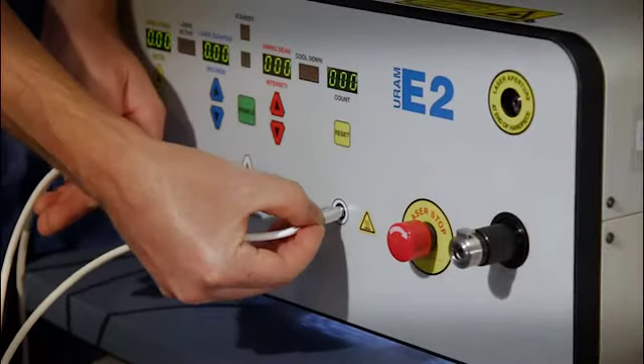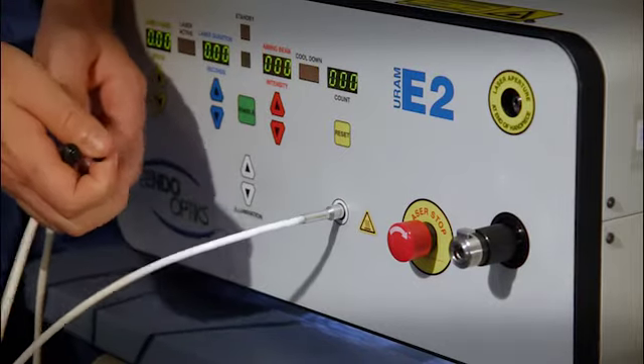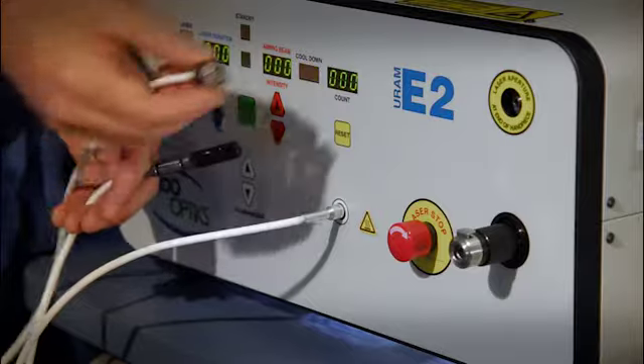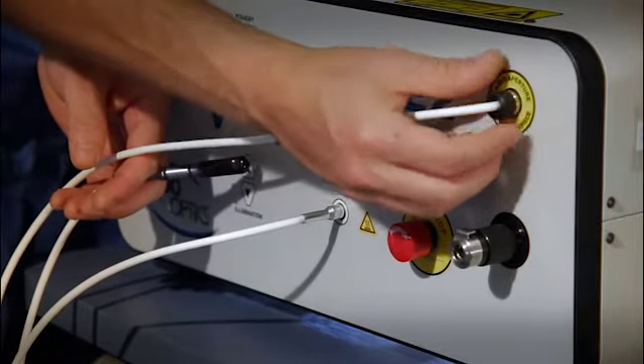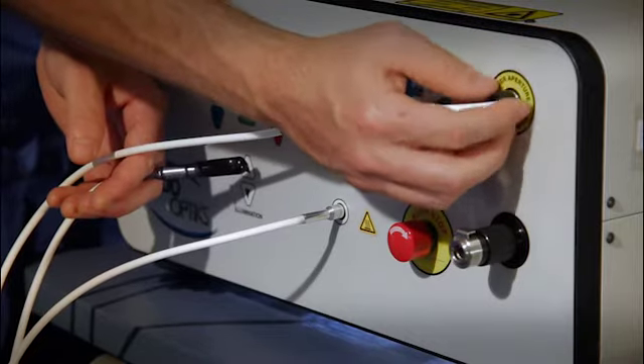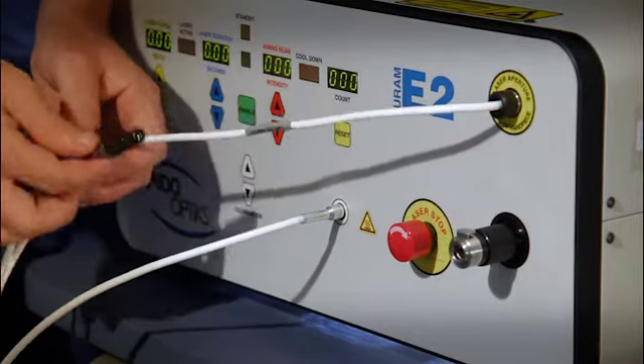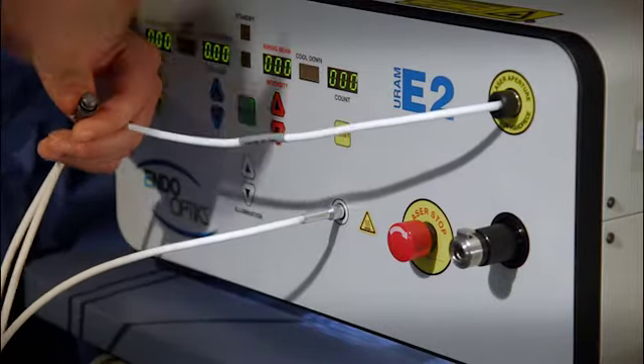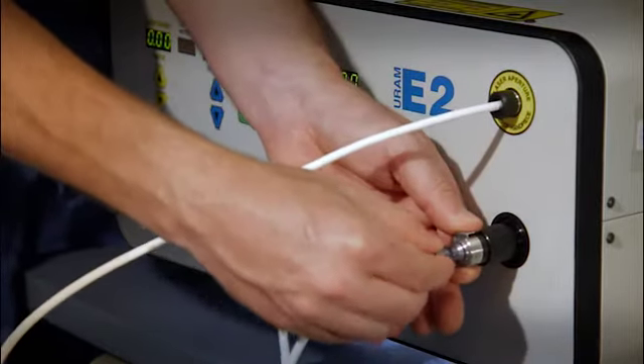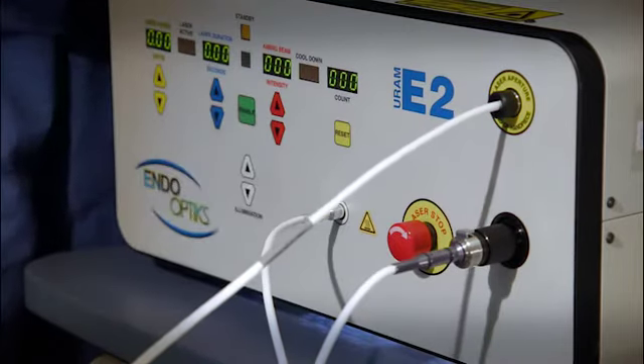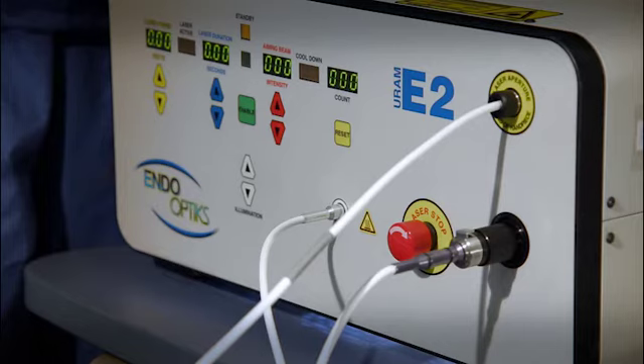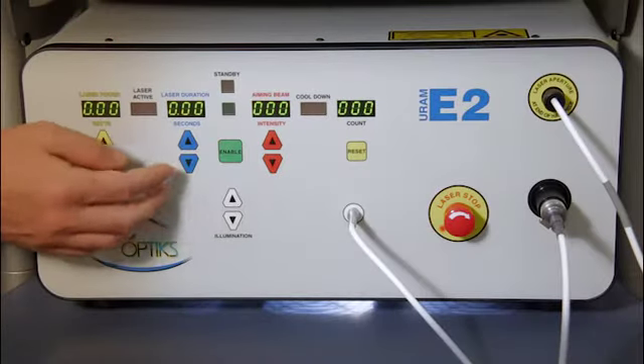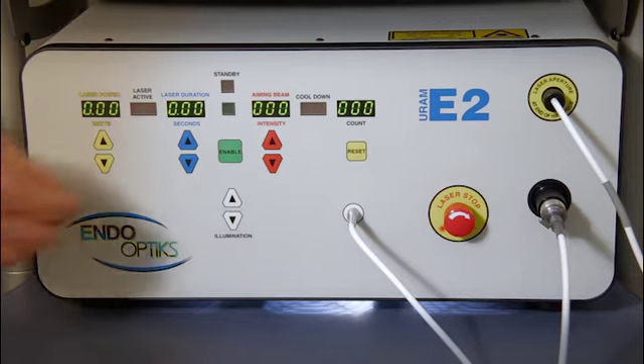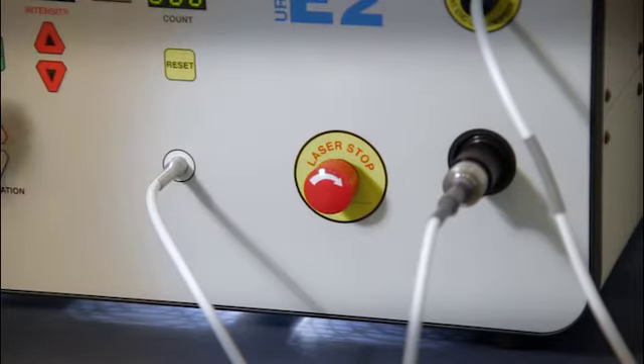There is no set order for connecting the three ends, but the best technique is to insert the light first, and then screw the laser connector into its port. Now you can push the lever on the video adapter with one hand, while inserting the video connector with the other until it clicks into place. If your laser key is turned on with the laser connector in place and the red stop button out, you will hear an audible tone indicating that the laser has been activated. If you do not hear this tone, make sure the laser stop button is in the out position. A small clockwise twist will assure it is set properly.